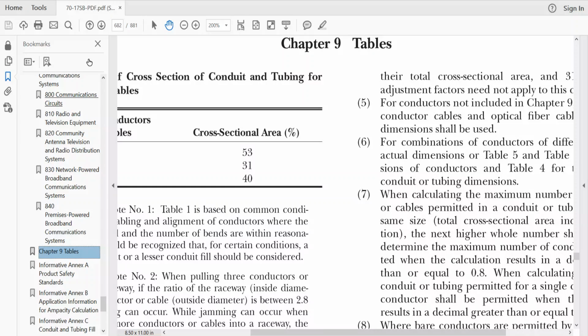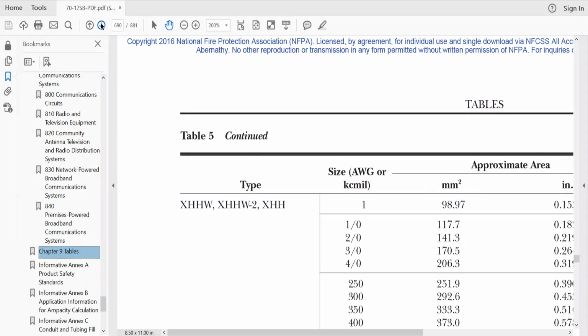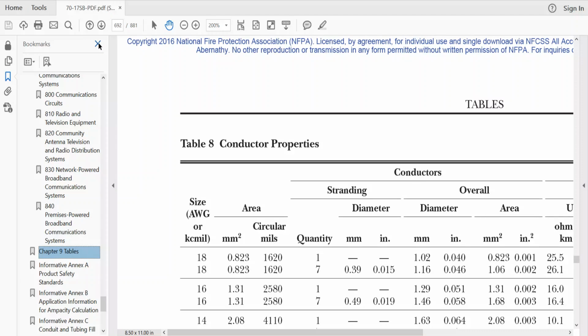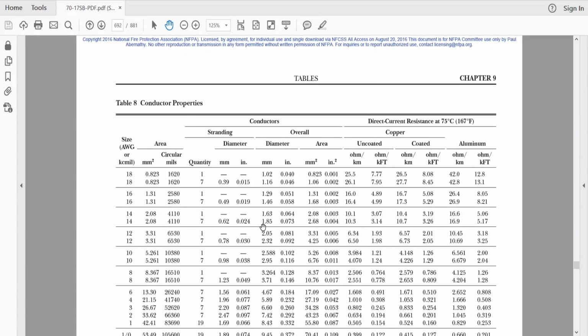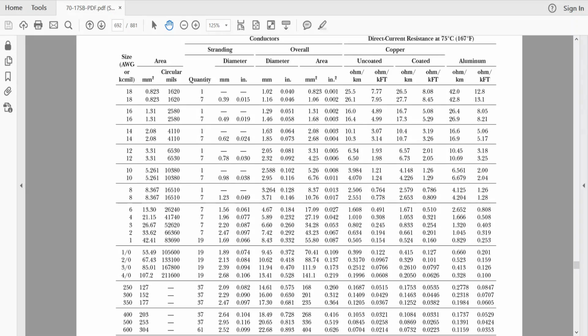We're going to go through the tables and find Chapter 9, Table 8. Oh, I went one too far. Okay. So let's reduce this down so we can see the whole thing. All right. So we said that we needed 167,000. In fact, let me look here. No, we need 187,500. So when we need 187,500, we have to find a conductor in those circular mils that is going to be adequate for that. So in this case, what if we picked a 3/0? Well, that's only 167,000 in here. That's certainly not enough. It's about 20,000 circular mils short. So we have to go to the next one. In this case, it would be a 4/0, which is 211,600. That's what we're going to need to use in this application.